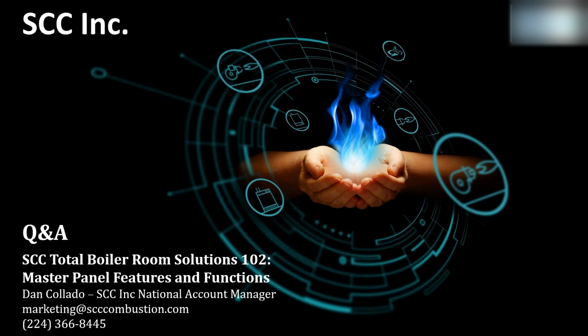Speaking about a steam boiler application where we have an existing LMV3 or an LMV51, and we have no touchscreens at the burner itself or a PLC, can I monitor the boiler's stack temperature from the master panel and generate an alarm output? Yeah, great question. The answer is yes.